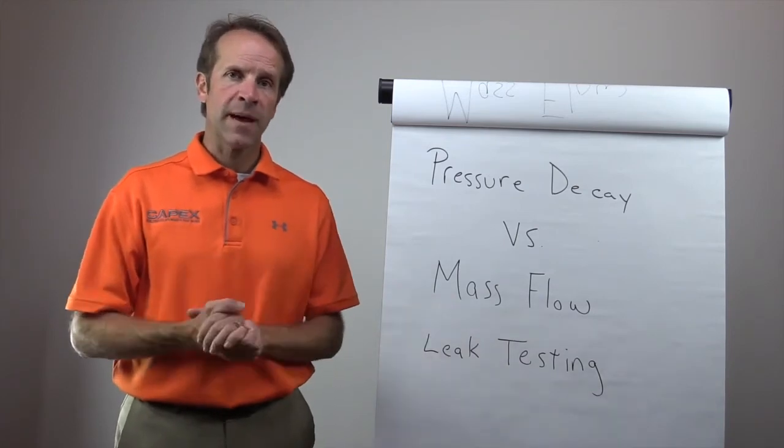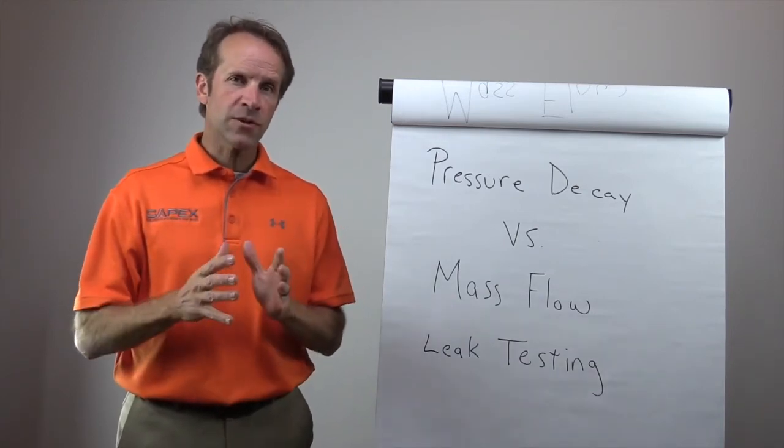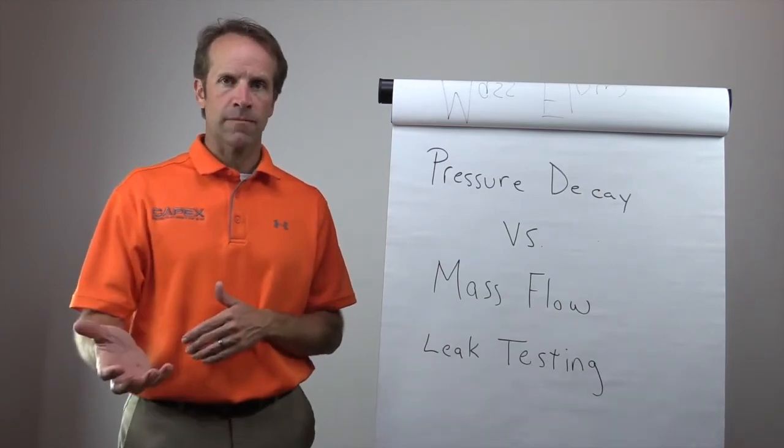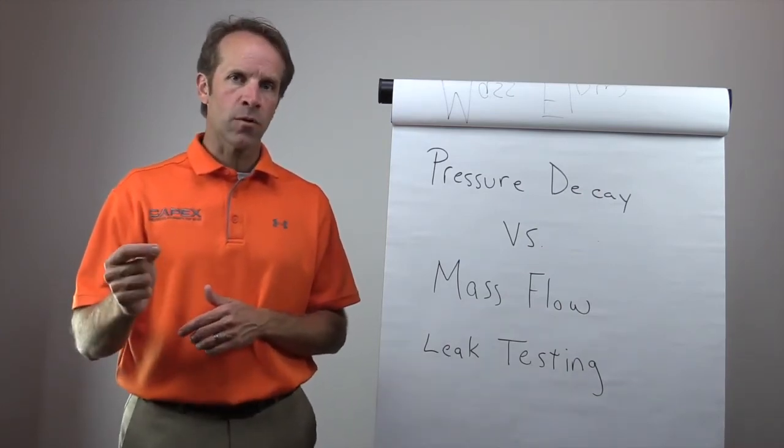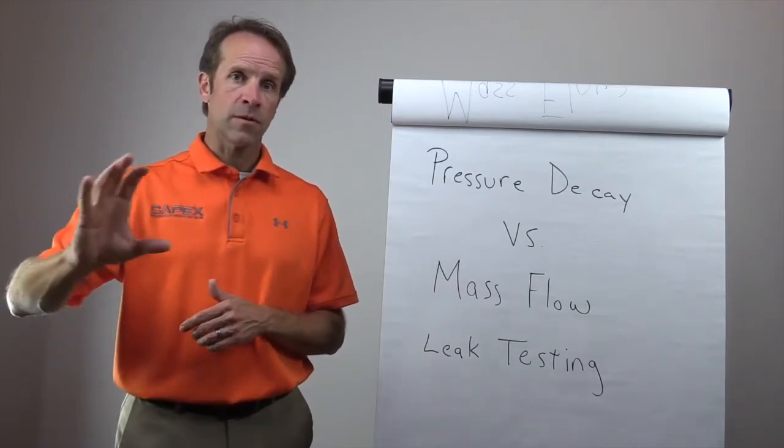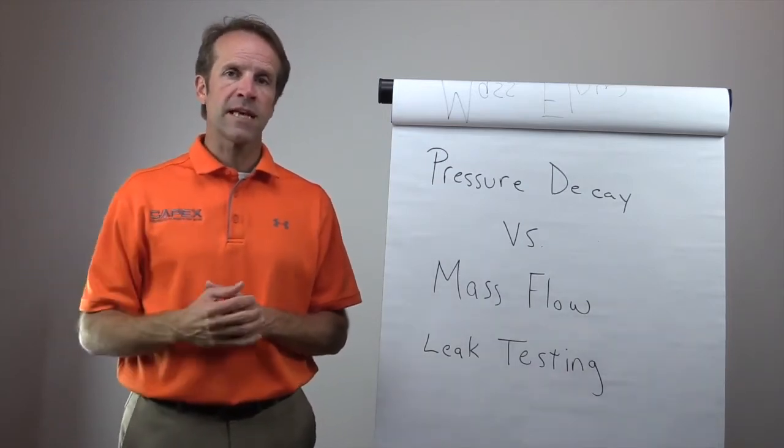Now, mass flow. The definition of mass flow is that we're measuring the amount of flow that it takes to maintain pressure in the part. We're measuring the amount of flow through a flow meter into the part. So the amount of flow that it takes to maintain pressure in the part.